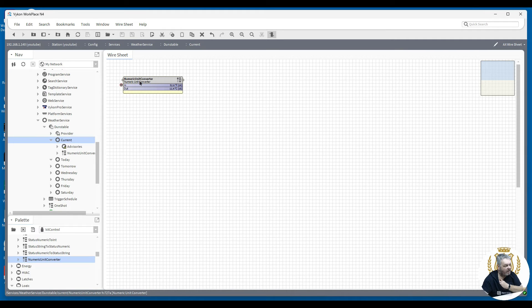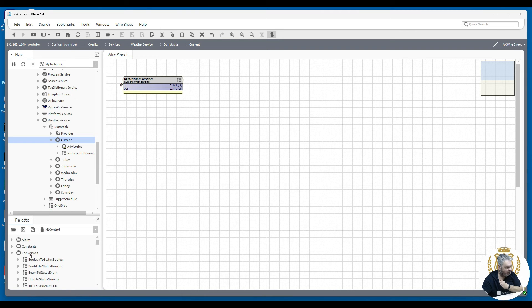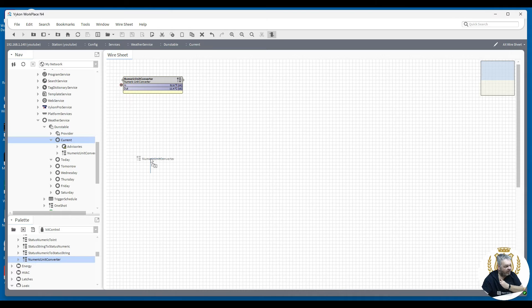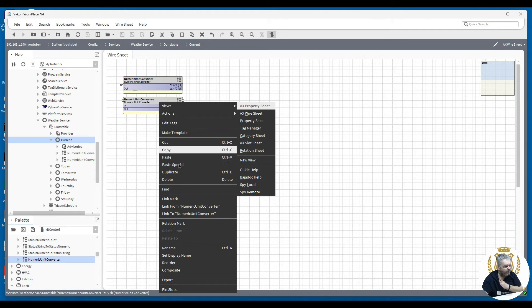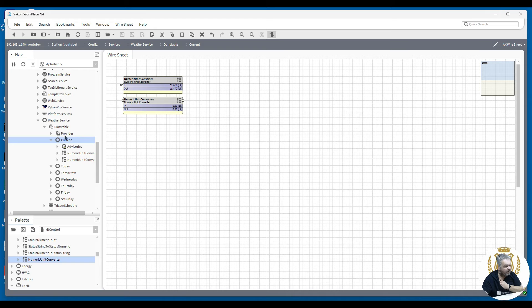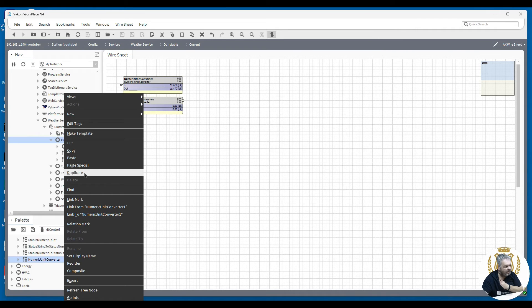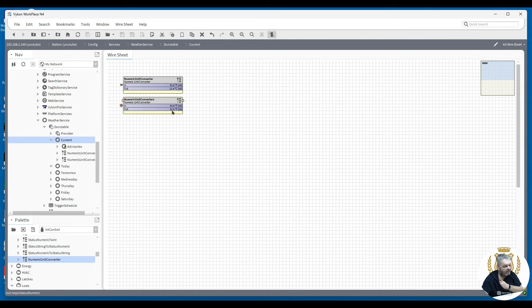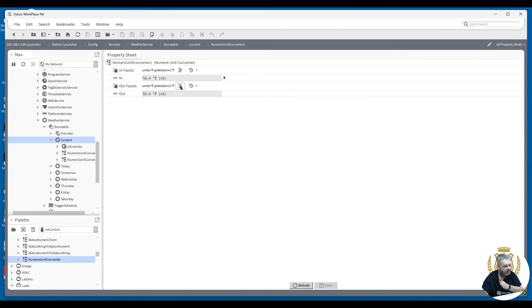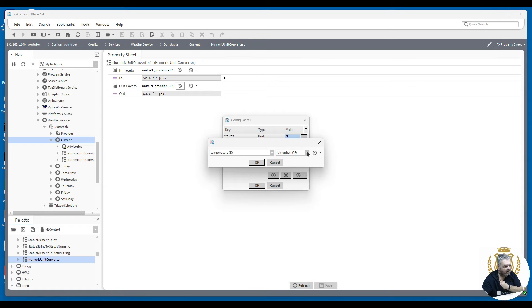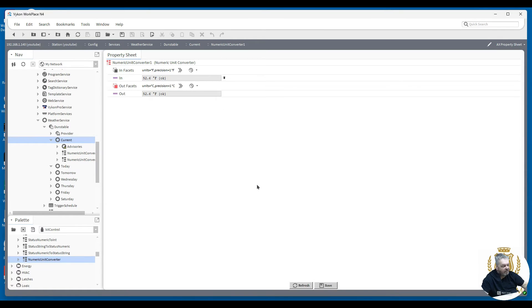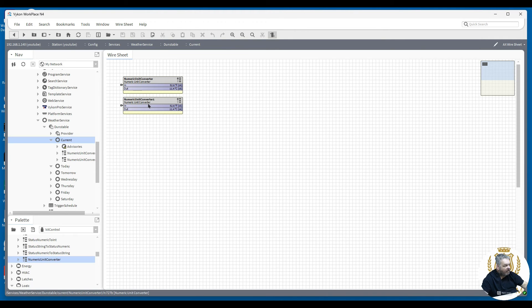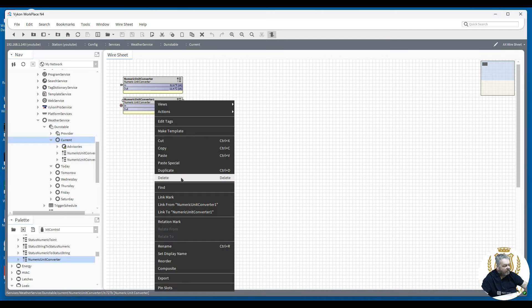So use a numeric unit converter — you'll find this in the kit under Control > Conversions. Drag one across, as I've done here above the link marker, where you've got your current day-link to temperature showing 52.4 degrees Fahrenheit. Change that to Centigrade, save, and that's done the conversion for you.